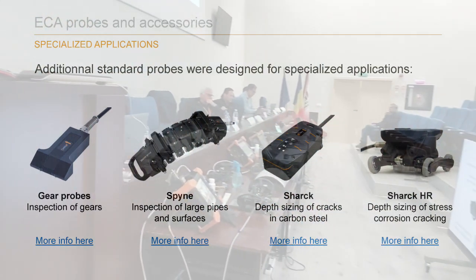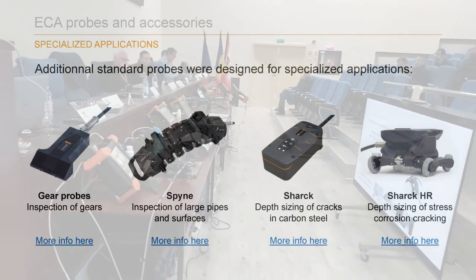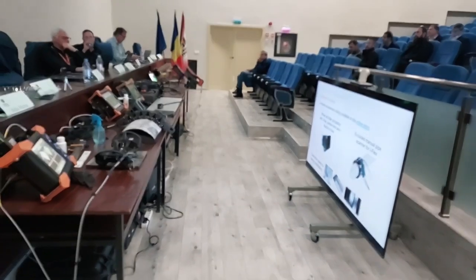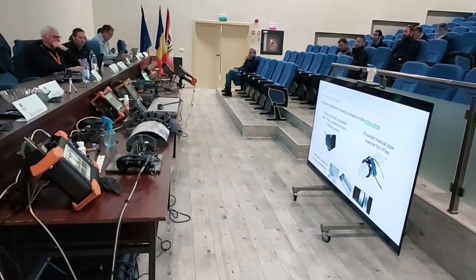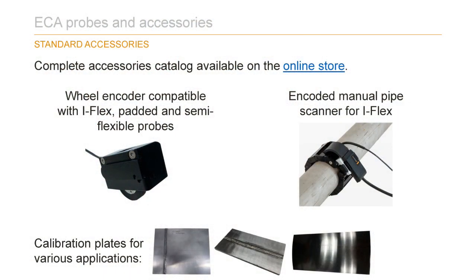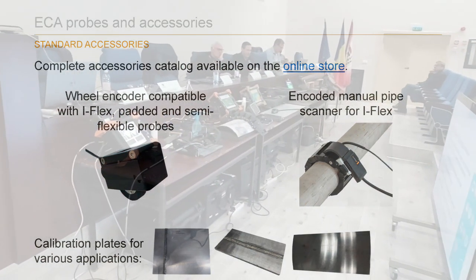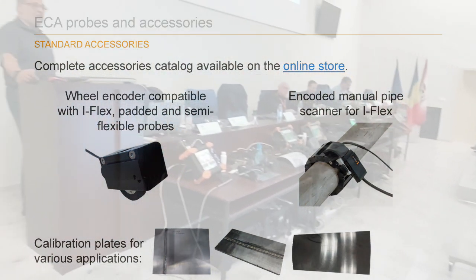Different accessories of course: encoder, dedicated encoder, a manual scanner for example. And we have a set of different calibration blocks, welded or not welded, made of aluminium, made of stainless, made of carbon steel. You can have all types of conductive material. I forgot to say, but eddy current of course is only applicable on conductive material.